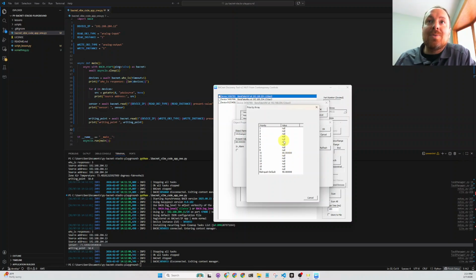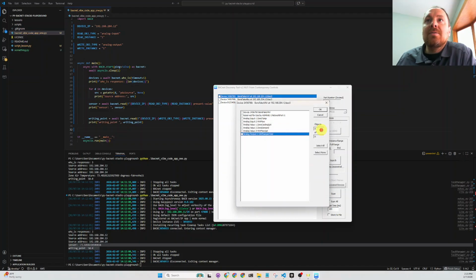Never write higher than the building operator, because typically these are left for life safety. It's very rare, I've only seen this once or twice, that there is a complicated smoke control sequence that the engineers designed, or fire alarm or something, where logic happens above the building operator that they can't release. It will happen up here. So just keep that in mind. That's what priority means in BACnet. There's 16 priorities, and we're playing around with 8. So that's where it's written.